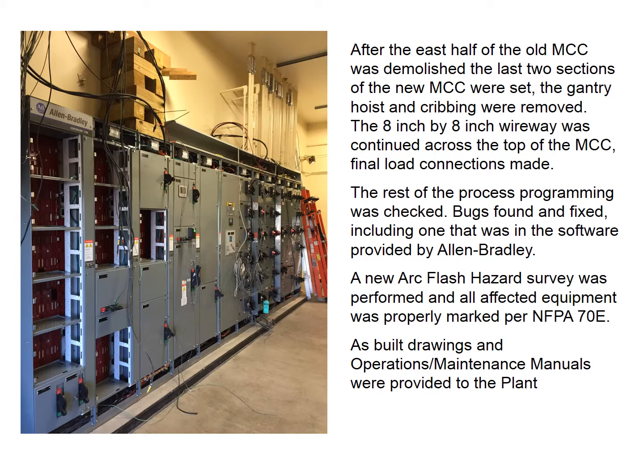The rest of the process programming was checked, bugs found and fixed, including one that was in the software provided by Allen Bradley. A new arc flash study was performed and all affected equipment was properly marked per NFPA 70E, and as-built drawings, operation and maintenance manuals were provided to the plant.